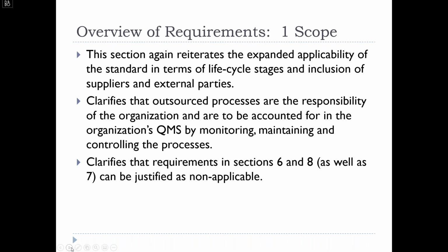Many organizations seeking certification to 13485 are outsourcing their manufacturing process either partially or wholly to a contract manufacturer. As part of our 13485 audit, we need to verify the integrity of that outsourced process. How are you ensuring that it's done in a controlled manner? Are you conducting audits of that contract manufacturer?